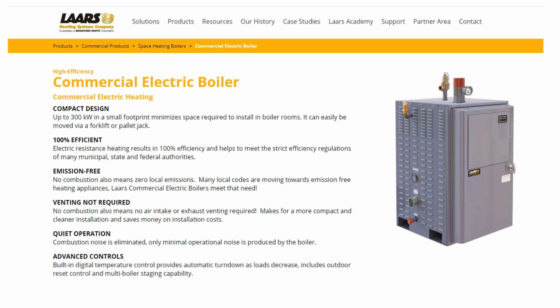So we move on. LAARS also has answered the call on the electric side. So with the calls for electrification, we first released this resistive technology boiler. It's up to 1 million BTUs in a 300 kW model. It's a very small footprint. You can drag this thing in and out with a pallet jack, or obviously a forklift. It's 100% efficiency because of the resistant technology, and it can be used emission free because it doesn't have any venting, so no venting requirements.